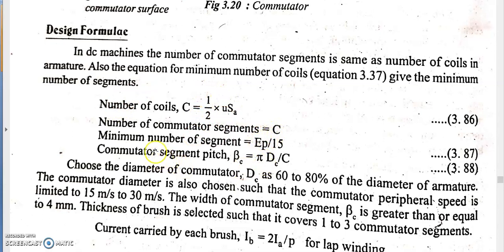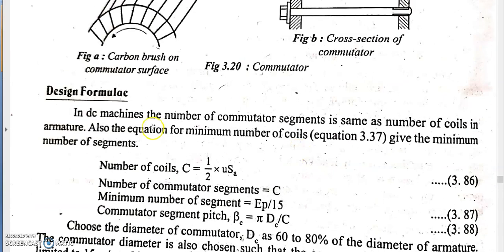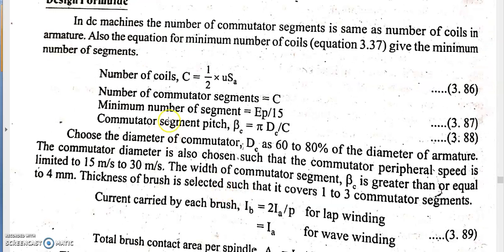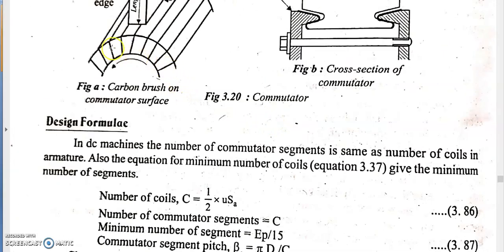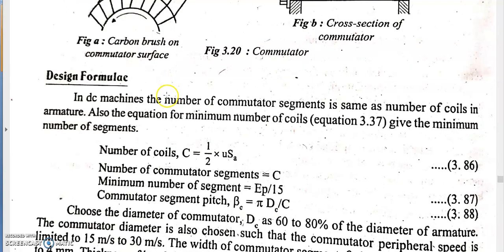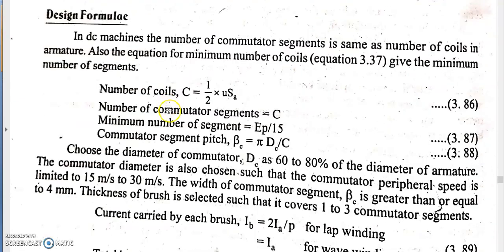The minimum number of commutator segments must be EP/15. A larger number of commutator segments is advisable so that the voltage between adjacent segments is lower. However, there is a minimum limit. If this minimum is not maintained, the amount of spark produced will be more. To improve the commutation process and achieve sparkless commutation, the minimum number of commutator segments must be maintained as EP/15.